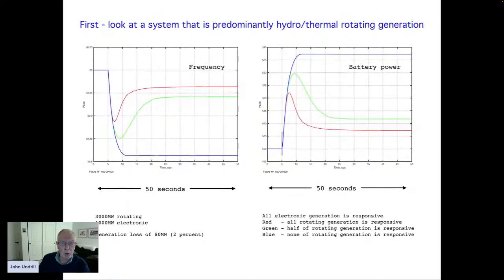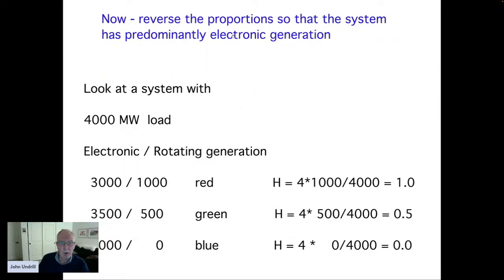Now let's reverse the discussion. Instead of a system that's predominantly rotating, hydro and thermal, let's look at a system that's predominantly electronic, with a little bit of leftover rotating capacity. So let's look at this 4,000 megawatt system: 3,000 megawatts electronic, 1,000 megawatts of rotating generation. Its inertia constant would be 1, but we're not going to worry about that too much. But for those that really want to know, the inertia constant would be 1. If you cut the rotating generation in half, it would be 7/8 electronic.